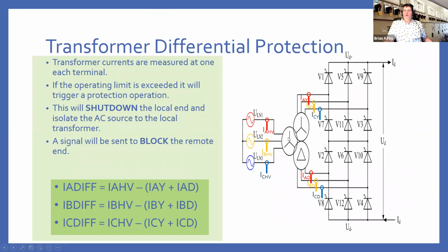Also on the transformer, there will be a form of differential. So typically you will have a star on the AC side and a star delta arrangement on the DC side to give you a phase shift between the two legs of your converter station. And your differential works the same principle as on AC. The sum of the currents on the low voltage on the DC side should be the same as the currents on the high voltage AC side. And again, if you have a fault, you block the remote end and you isolate and shut down the local end.